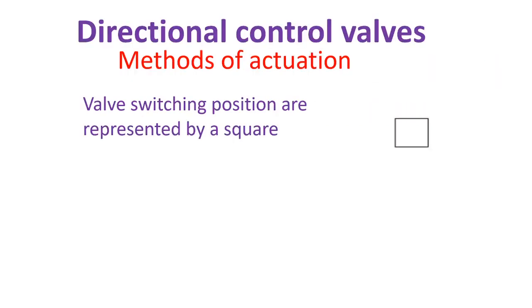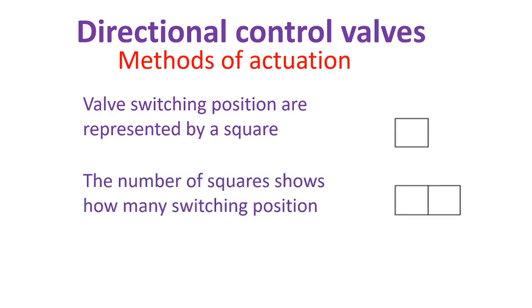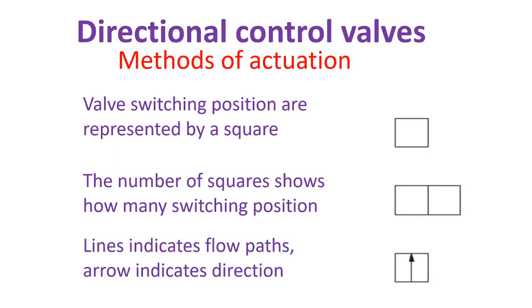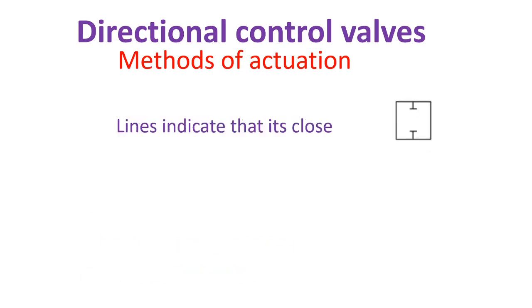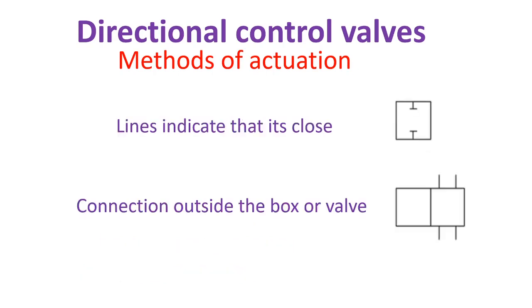Now let's get started on how to read directional control valves. Valve switching positions are represented by a square. The number of squares shows how many switching positions there are. Lines indicate flow path, arrows indicate direction, and a line across the box indicates it is closed. Connections appear outside the box or valve.